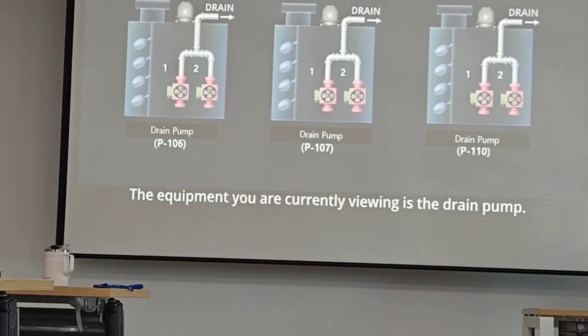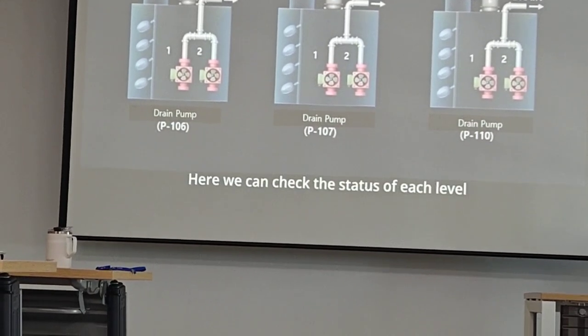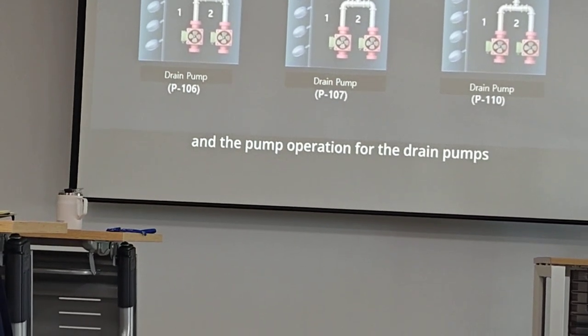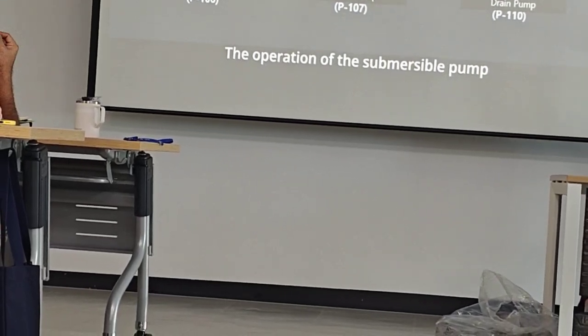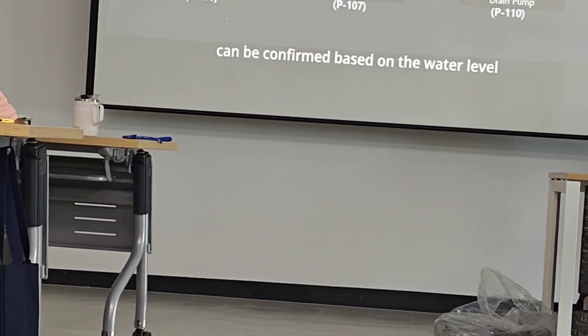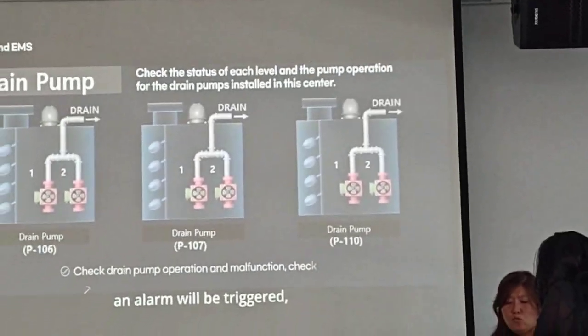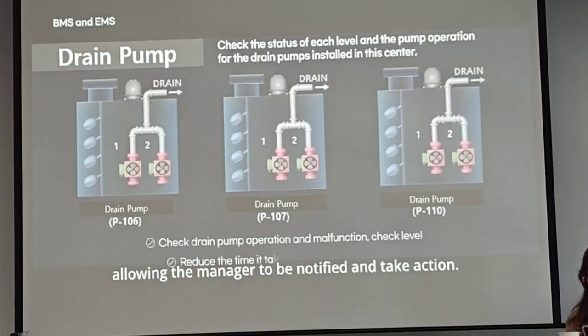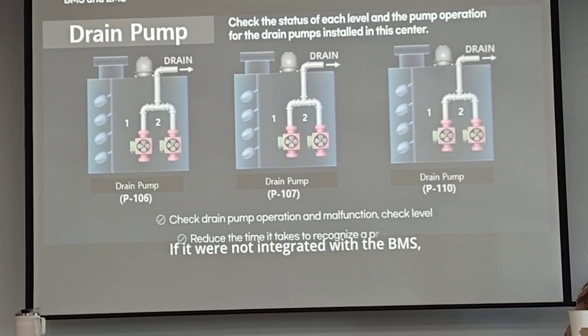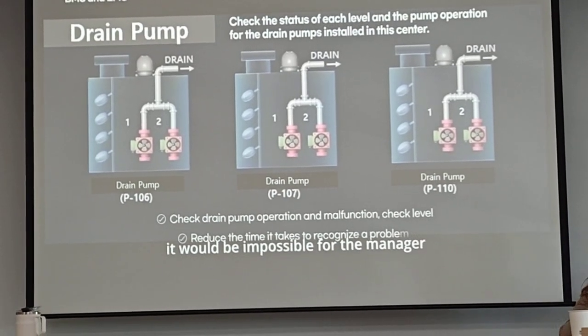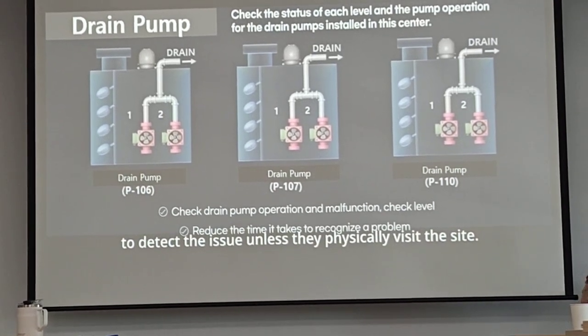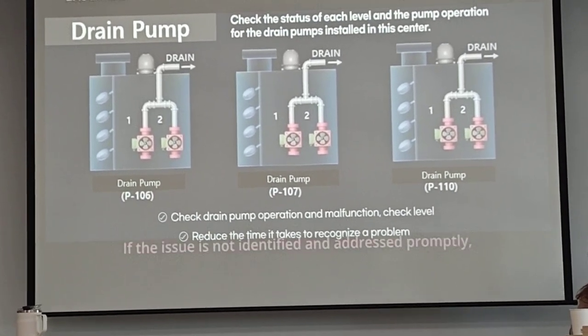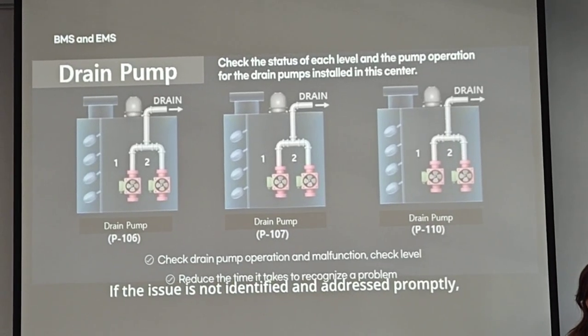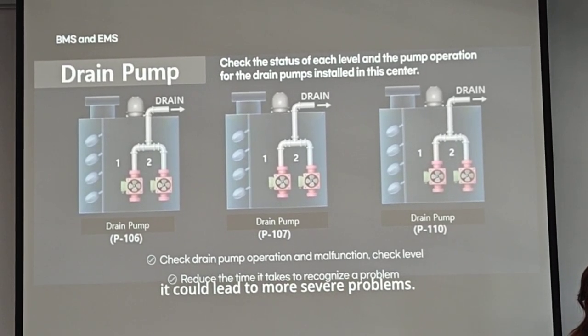The equipment you are currently viewing is the drain pump. Here, we can check the status of each level and the pump operation for the drain pumps installed at this center. The operation of the submersible pump can be confirmed based on the water level, and if there is an issue with the level or pump, an alarm will be triggered, allowing the manager to be notified and take action. If it were not integrated with the BMS, it would be impossible for the manager to detect the issue unless they physically visit the site. If the issue is not identified and addressed promptly, it could lead to more severe problems.